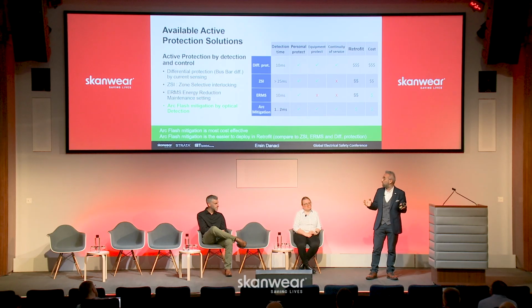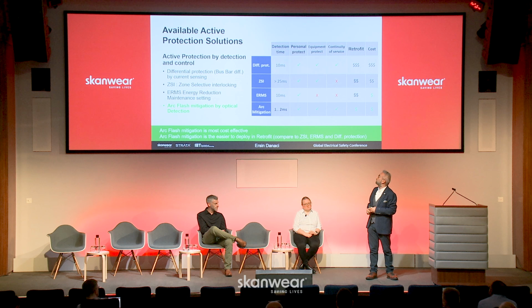And if you count the circuit breaker operation time, which is around 50 to 80 milliseconds, we will be able to isolate the faulty circuit in less than 100 milliseconds. Because over 100 milliseconds, the explosion could, the result could be death. For that reason, we need to isolate the faulty circuits as soon as possible.